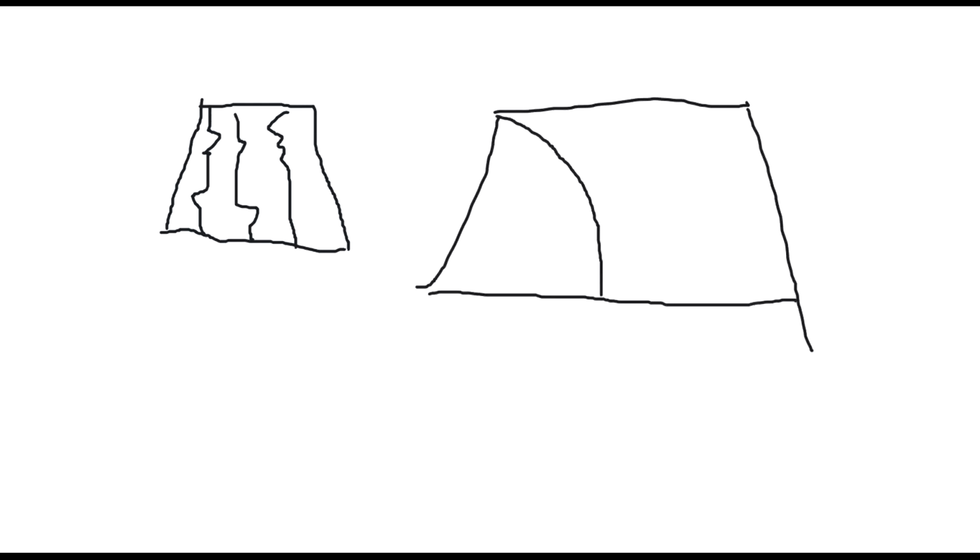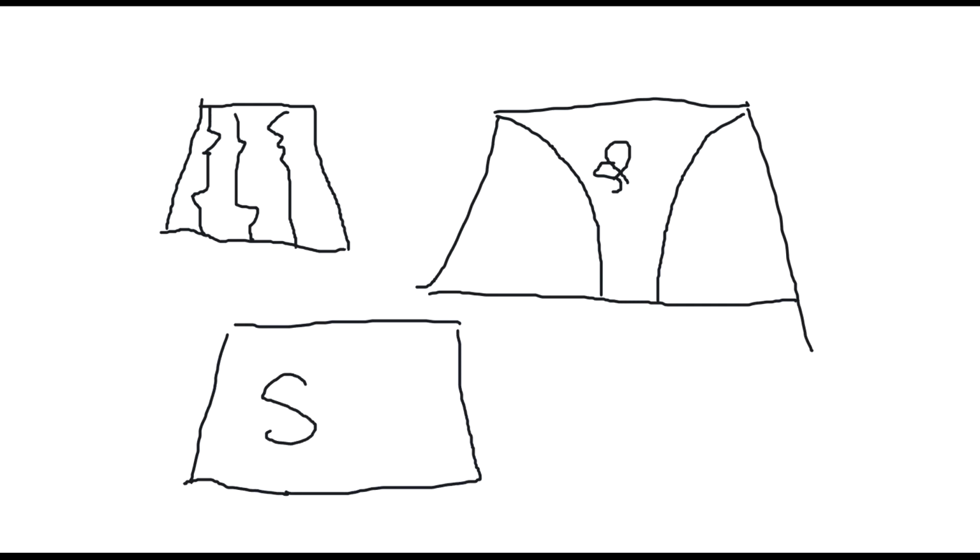And when we look at our spatial intensity, the portion that's the most intense is going to be proximal and down the center of our beam, right? So this is our spatial peak. And then we can take an average of all these intensities, so the spatial peak as well as the intensities outside of our spatial peak, and this becomes our spatial average.